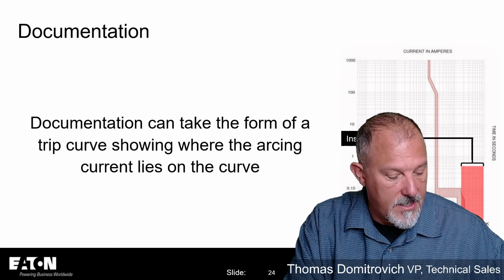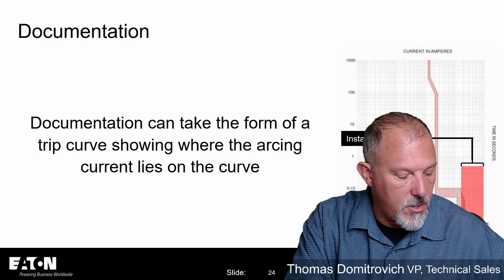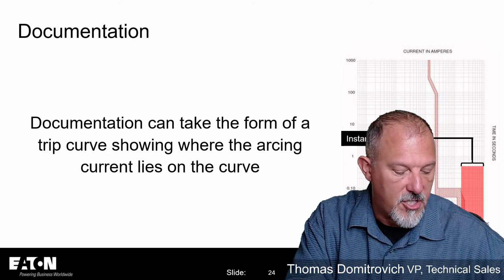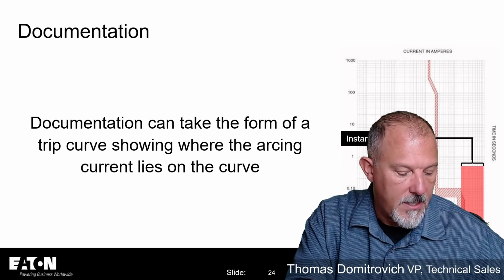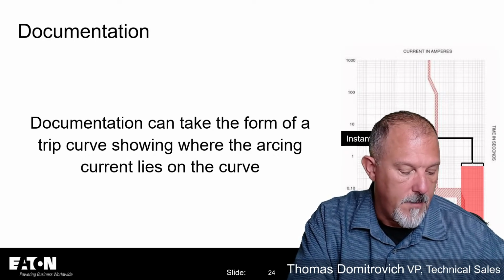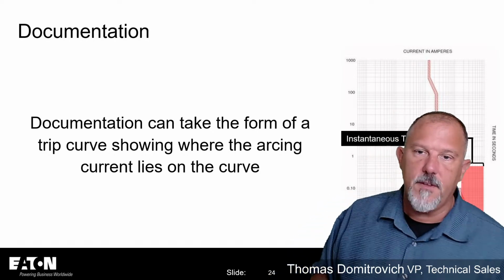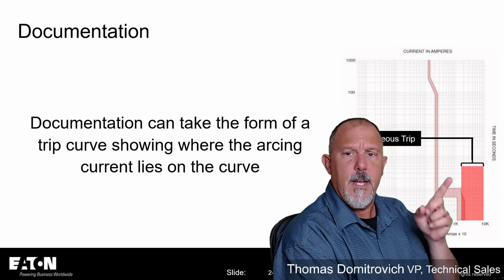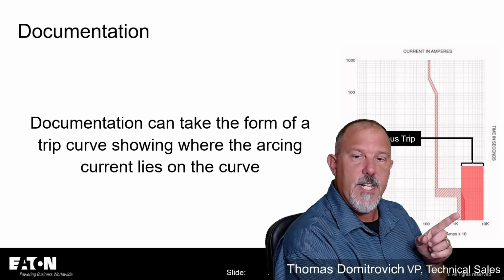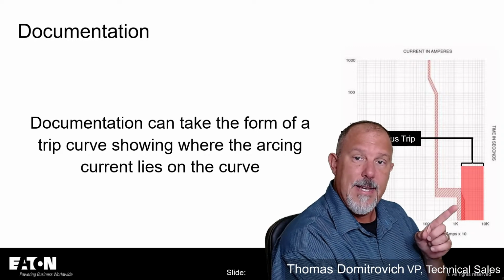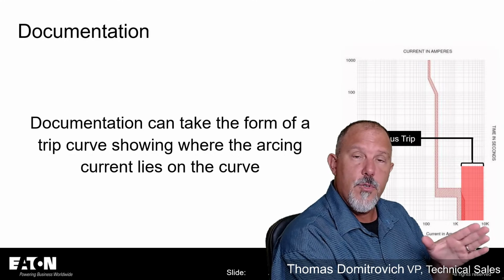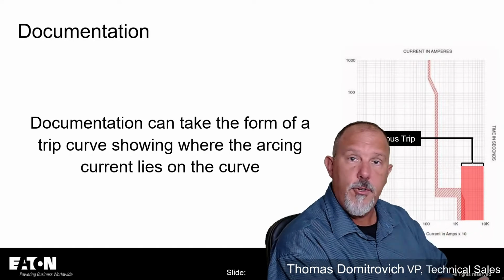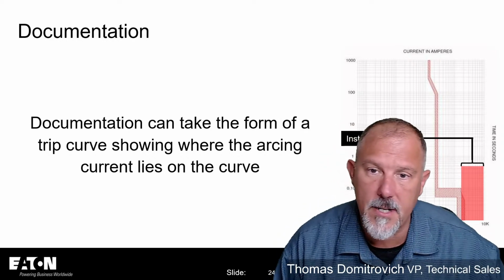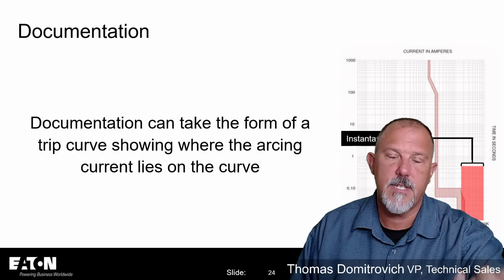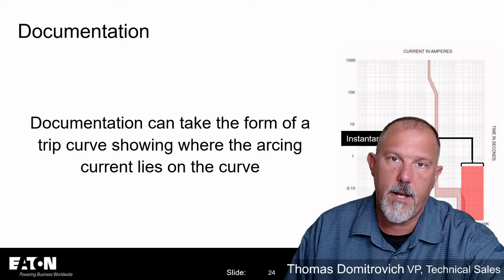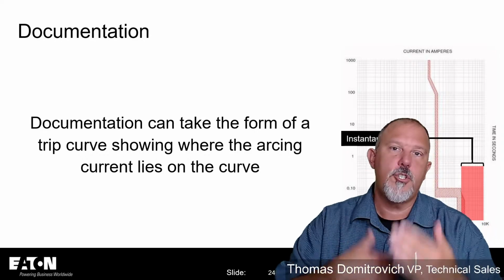Yeah, it doesn't even say in here that it has to be... documentation shall be available to those authorized to design, install, operate, or inspect the installation. Documentation shall be provided to demonstrate that the method chosen to reduce the clearing time is operating below the available arcing current. So like on this one here, I've got the arcing current has to be in the instantaneous region, which has to be high enough over here to actually get into that instantaneous region. So somebody should show you a trip curve like this and show you the arcing current, or tell you, here's what the pickup point is for that instantaneous, and here's the arcing current in this application is whatever, and look, it's greater than that pickup point. So that's what you're looking for.